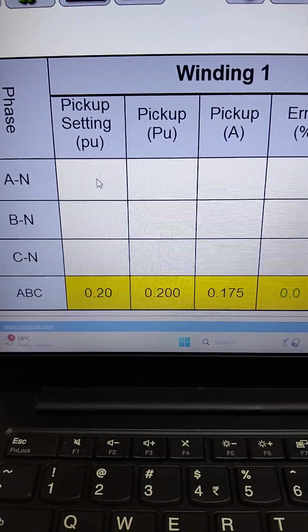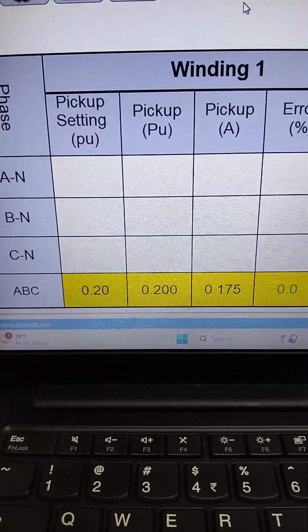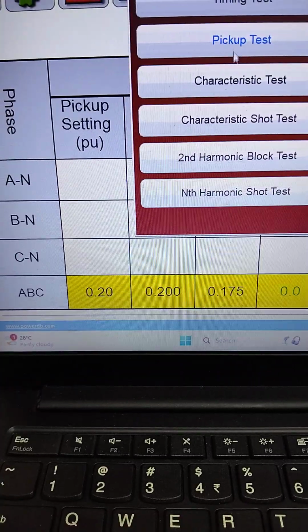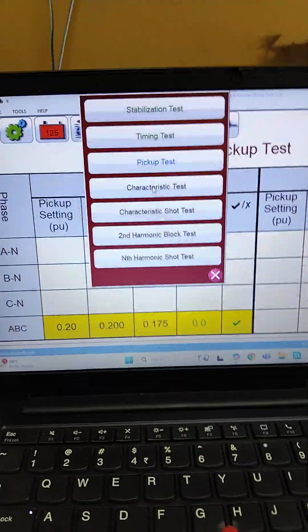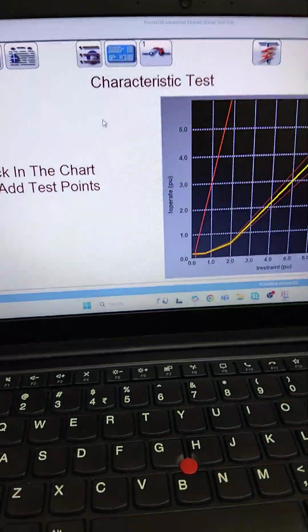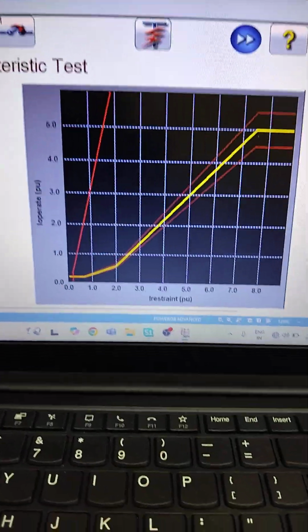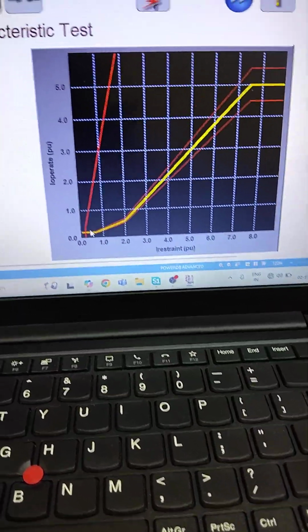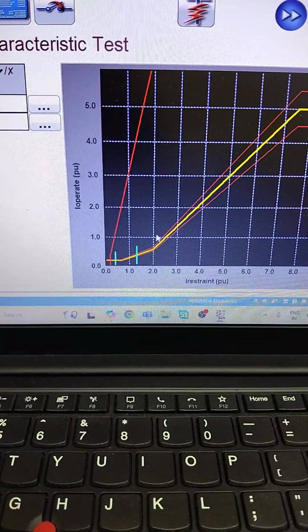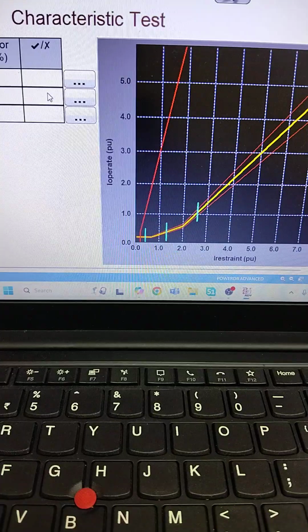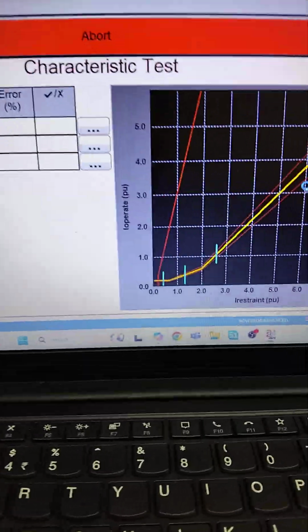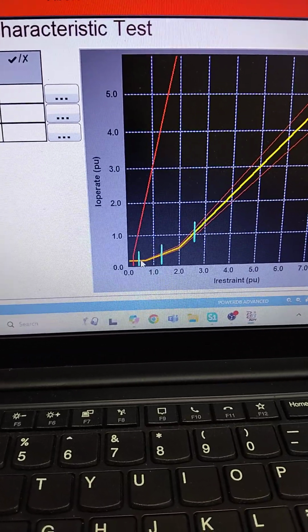Now if you are doing a single phase testing, in that case you need to check that there are some multipliers which you need to put in the settings tab itself, otherwise the test will fail. Now this is the characteristic, the 3 section slope of differential, very famous. So for this we can check in the flatter zone, we'll inject one test case. In the K1 section we'll inject one, and in K2 we'll inject another. So in this again the relay will slowly increase the differential current, and it will check whether your tripping is taking place exactly on this line or it is exceeding or not.